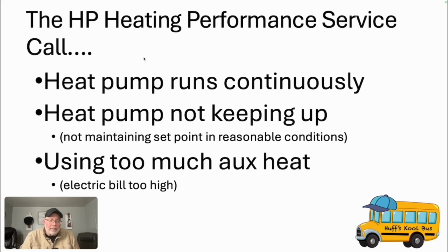And so, again, we're not going to get into load calculations. What we want to really center in on today is how can we determine what the heat pump is doing and what it should be doing, so that then we can move to the next issue, if you will, or be able to actually instill confidence in the customer that the system is working correctly.